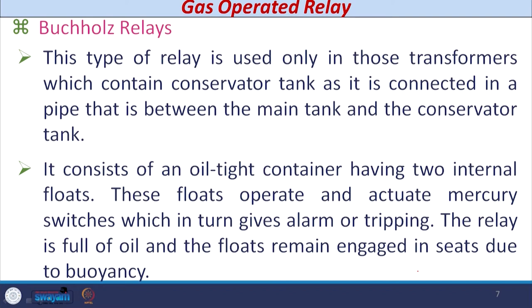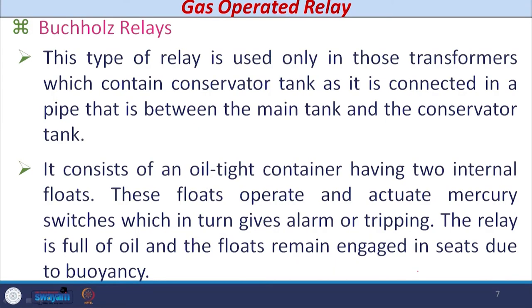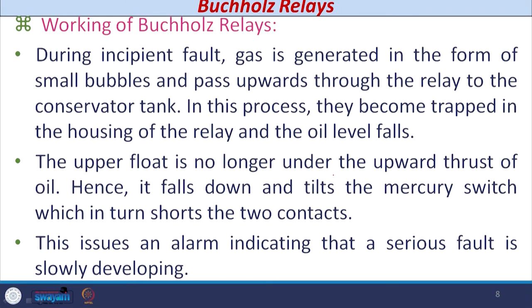The Buchholz relay is normally connected in the pipe between the conservator tank and the main tank of the transformer. This type of device is utilized particularly in our country, whereas sudden pressure relays are used in some other countries. The Buchholz relay consists of an oil-tight container in which two floats are provided. These two floats operate and actuate mercury switches located below each float. One is the upper float and the other is the lower float. The relay is full of oil and the floats remain engaged in their seat due to the buoyancy effect.